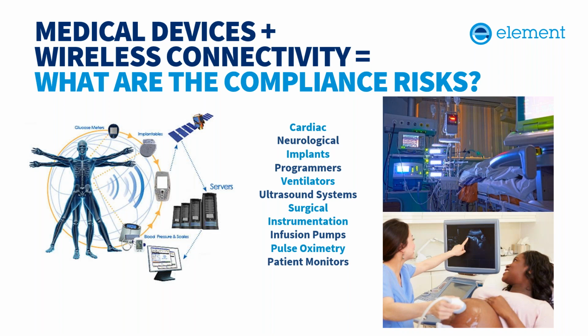Medical device advances that are saving lives every day rely on proper operation in their electromagnetic environment. And every year there are hundreds, possibly thousands of incidences of EMI in healthcare. So the FDA has a database, the MAUDE database, that tracks medical device malfunctions. And last time I checked, it had 250,000 reports of issues due to EMC. Between 2010 and 2019, there were 170 reports of deaths due to issues due to EMC, ESD, or wireless malfunctions.